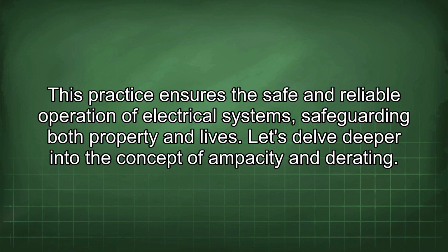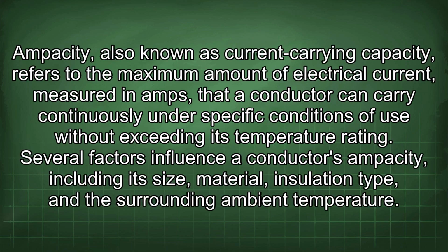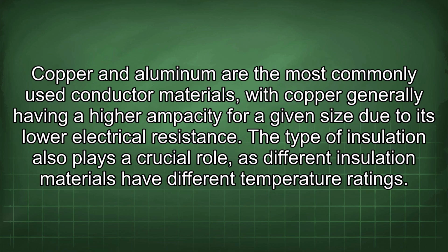Let's delve deeper into the concept of ampacity and derating. Ampacity, also known as current carrying capacity, refers to the maximum amount of electrical current, measured in amps, that a conductor can carry continuously under specific conditions of use without exceeding its temperature rating. Several factors influence a conductor's ampacity, including its size, material, insulation type, and the surrounding ambient temperature. Copper and aluminum are the most commonly used conductor materials, with copper generally having a higher ampacity for a given size due to its low electrical resistance.